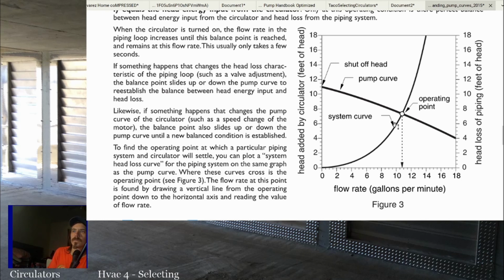And then you have the system curve. So this would be where the operating system would be at, right? So as you move down along the system curve at 4 feet of head, you're going to be moving at 6.5 gallons or so per minute. And then if you go up in feet of head, up at 14, you're going to be running about 12 gallons per minute. So anyway, you need to select a pump where the system curve is within your operating point.